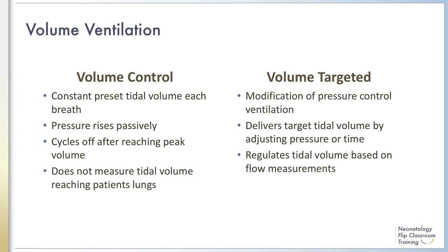This mode controls volume delivery into the ventilator circuit rather than the tidal volume that enters the patient's lungs. Volume measured at the ventilator does not account for the compression of gas in the circuit and humidifier, distension of the compliant circuit, or air leak around the endotracheal tube. These are the reasons why older generations of volume controlled ventilators were mostly impractical for use in small premature infants.